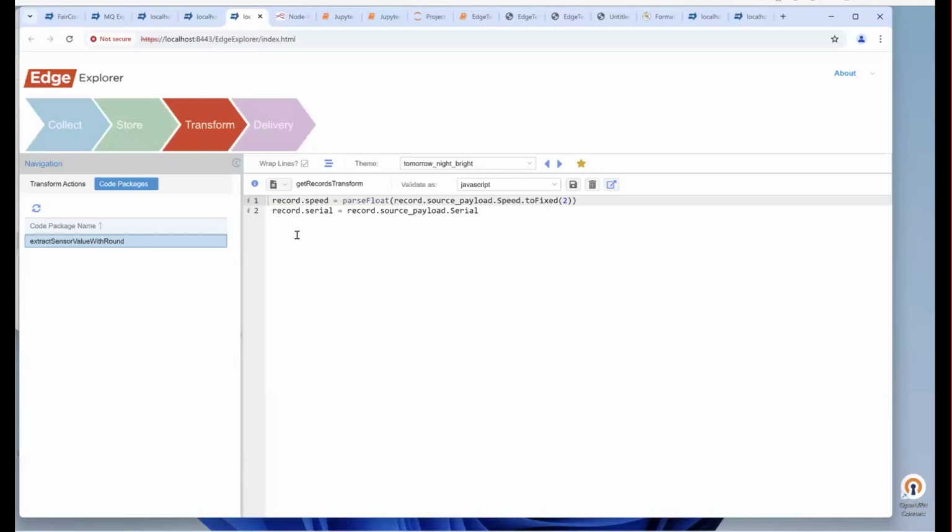So what this transform that I'm adding now would do is it takes that float value that I was getting that had a lot of decimals on it. I happen to know those decimals are not significant. The spindle speed sensor on this really is only good for about 2 decimals. So in order to not imply more precision than I have, I'm going to just round that to 2 decimals. So that's an example of a transform that I might want to add.